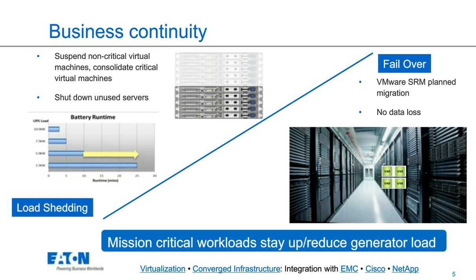And our third feature of business continuity is power capping. It's not on a slide, but it's very simple. When there's a power outage, we send a command to a server to throttle back. So if the server is running at 500 watts initially and you get a power outage, we can throttle that back to maybe 250 or 300 watts. Therefore, you save battery capacity, or if you're running on a generator, you lose less of the generator. It's not running as hard.